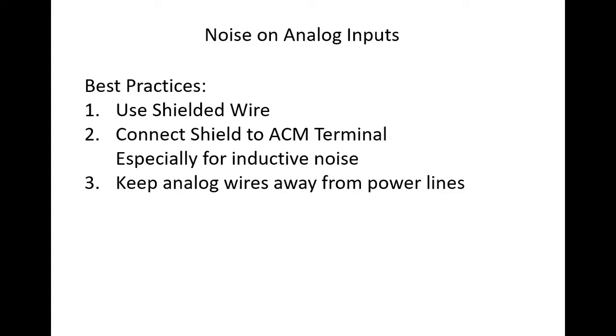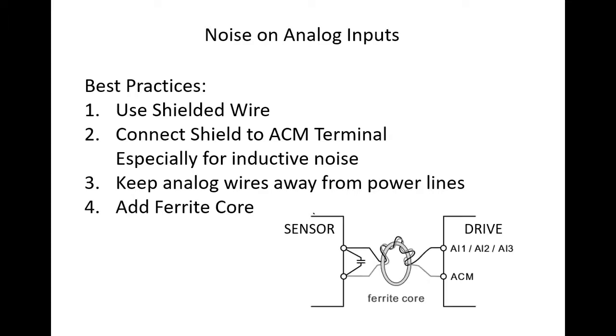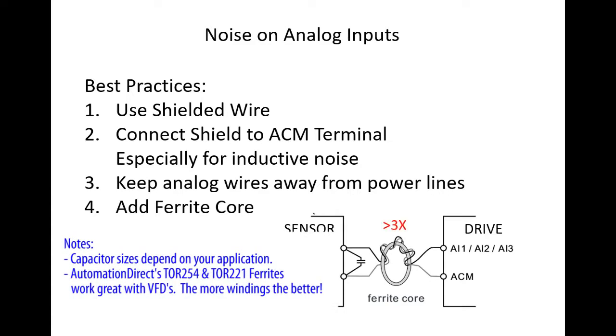Keep the wire away from long parallel runs with power lines or other noise-inducing wires. If the noise is coming from the AC motor drive, consider adding a capacitor and a ferrite core like this. Make sure the wire is wound around that core at least three times, more if possible.